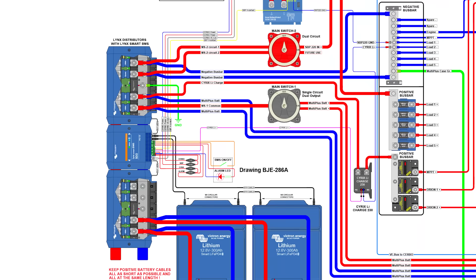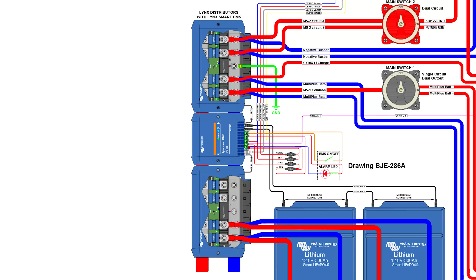Here on the schematic you can see that the Lynx Smart is interacting perfectly with the Lynx distributor. It's even so nicely integrated that you can read out through the Lynx Smart BMS what the status of your fuses are. So it interconnects with the Lynx distributor, and then the whole overview of your DC system will be visible on the VRM side. Of course, the Lynx Smart BMS has a Bluetooth connection, so you can set it up quite easily. It has a 500 amp contactor, and it will also work with pre-alarm. So before switching off at an alarm status, you can also enable an alarm for a buzzer or an LED to warn you that something is about to happen.